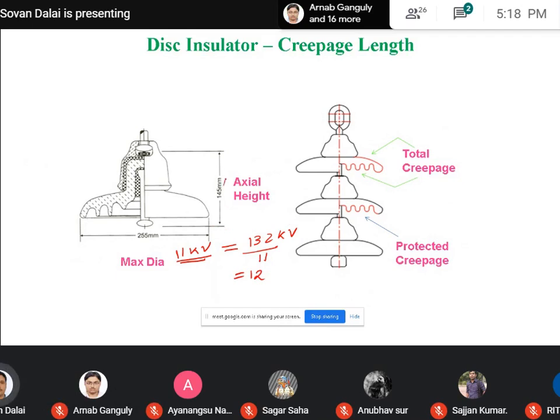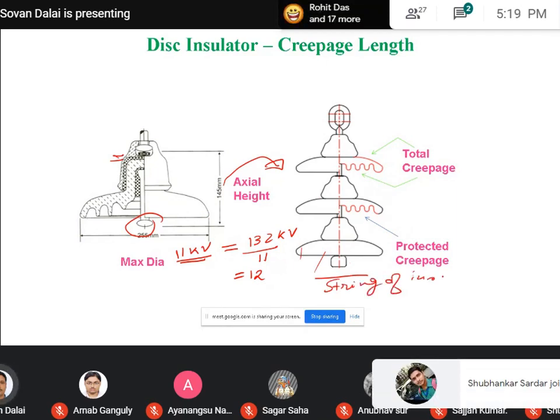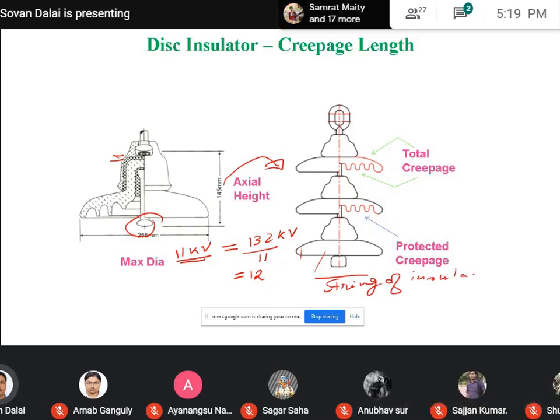And for that reason, here we want to show how these insulators are connected one by one. The bottom portion of one insulator is connected to the top side of another insulator. In that way, according to the voltage level, you can gradually increase the number of discs in a particular string. When you connect more than one disc in that formation, that is basically called a string of insulator. And here two things are marked: one is called the creepage distance and another is called the protected creepage distance.